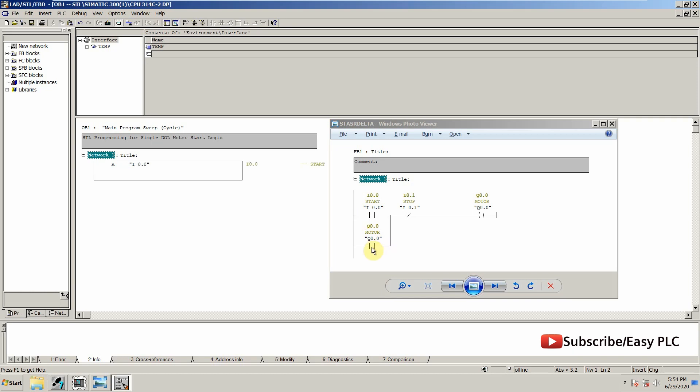Now this output contact Q0.0 is in parallel to the start button, so we have to use OR operation. O will be the OR operation. Q0.0 will be our motor contact.